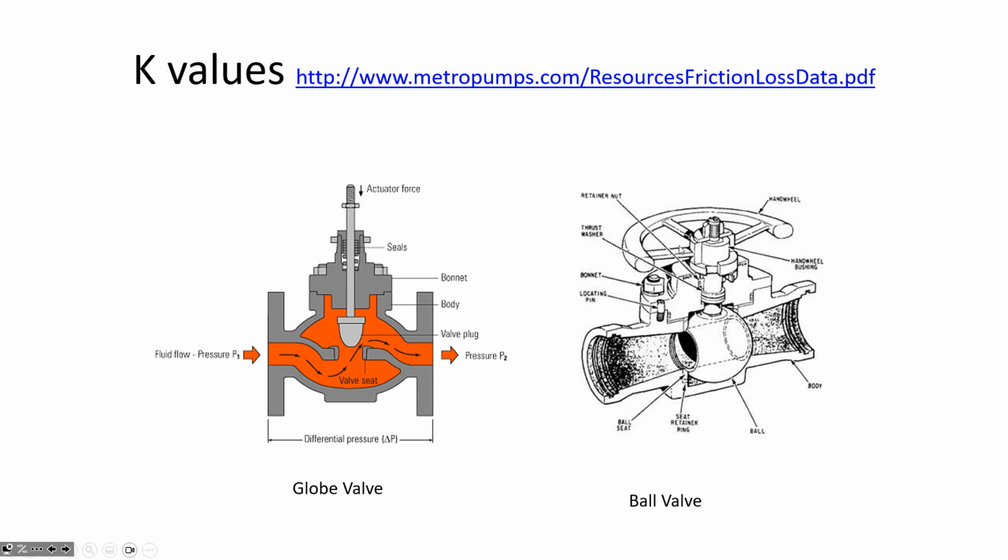And compare that, contrast it to a ball valve. When water's flowing through the ball valve and it's open, the diameter has just contracted a little bit. We can see that this is flared. You can see that there's a taper there. The incoming pipe diameter is a little bit larger than the water through the ball. The diameter through the ball is smaller, but not compared to the globe valve.